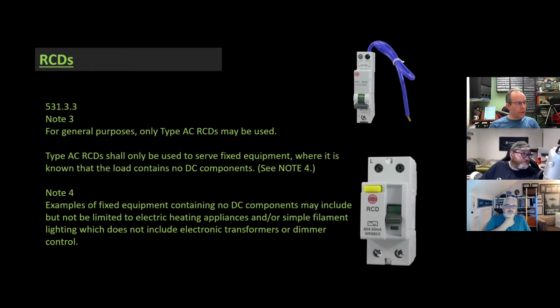What it actually says now is that for general purposes, only Type A RCDs may be used. Type AC RCDs shall only be used to serve fixed equipment where it is known that the load contains no DC components - that's note 4, underneath. Basically there aren't any, it's electric heating and filament lighting, which basically nobody uses anymore.